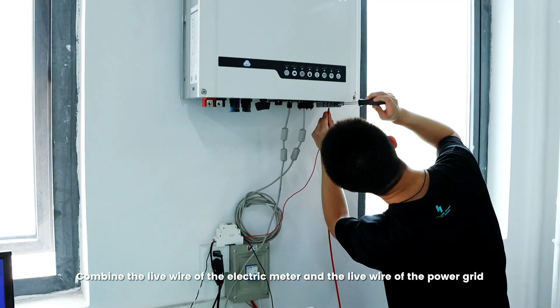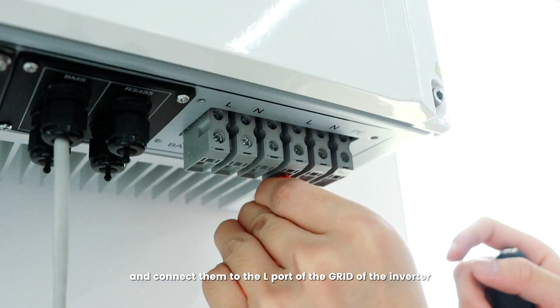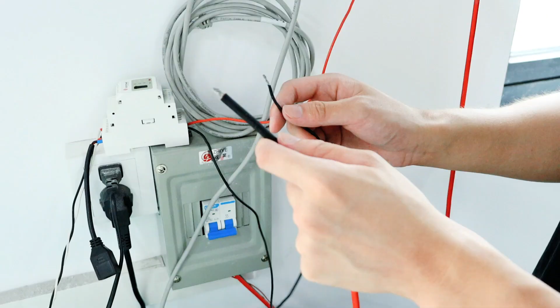Combine the live wire of the electric meter and the live wire of the power grid, and connect them to the L port of the grid of the inverter. Combine the neutral line of the meter and the neutral line of the power grid, and connect them to the N port of the grid of the inverter.